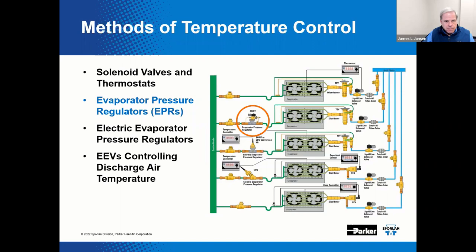Here's another way to control temperature with pressure regulators that simply control pressure. Evaporator pressure regulators control evaporator pressure — it's really just that simple. The refrigerant in the evaporator is saturated; by controlling the pressure in the evaporator, the associated saturated temperature will ultimately result through this control method. There is a correlation between the saturation temperature in the evaporator and the discharge air temperature, or DAT — also called leaving evaporator temperature or supply air temperature — based upon the heat transfer characteristics of the evaporator. EPRs are designed to provide a means of accurately maintaining evaporator pressure and a consistent temperature under varying evaporator load conditions.